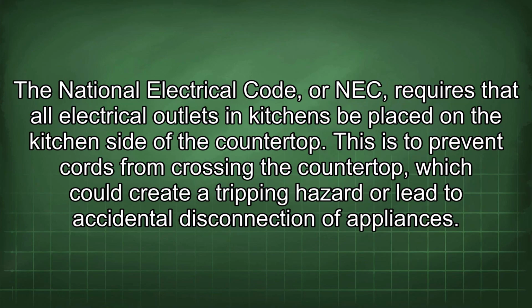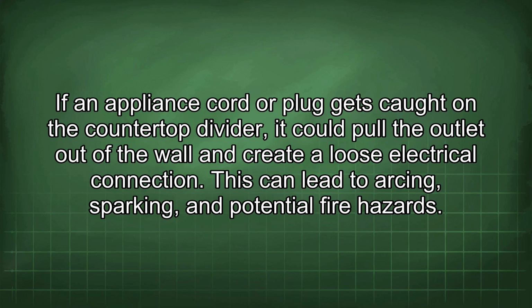The National Electrical Code, or NEC, requires that all electrical outlets in kitchens be placed on the kitchen side of the countertop. This is to prevent cords from crossing the countertop, which could create a tripping hazard or lead to accidental disconnection of appliances. If an appliance cord or plug gets caught in the countertop divider, it could pull the outlet out of the wall and create a loose electrical connection. This can lead to arcing, sparking, and potential fire hazards.